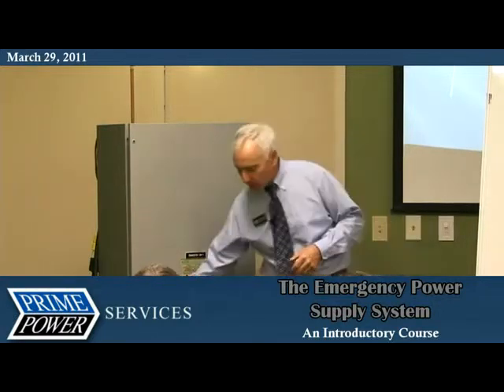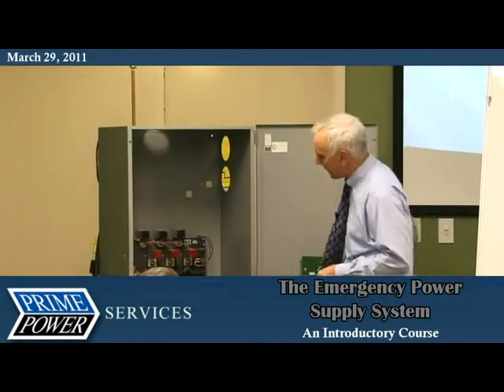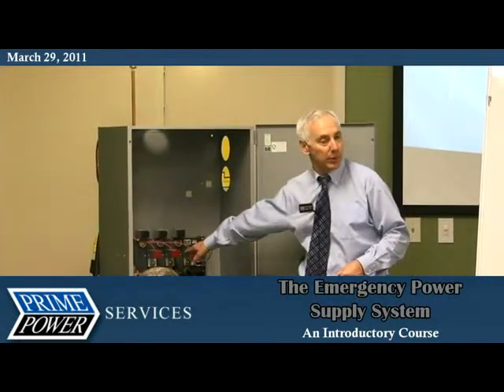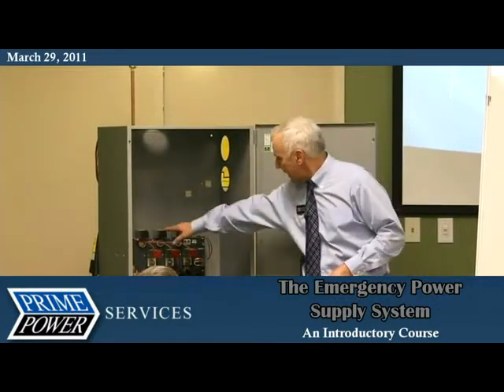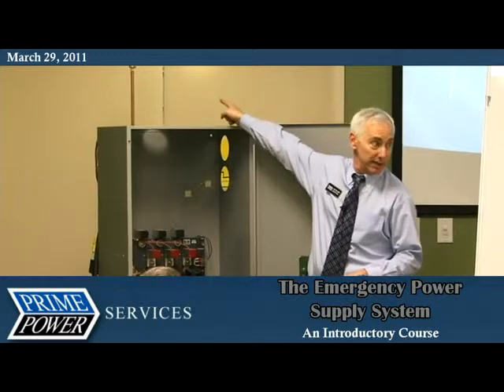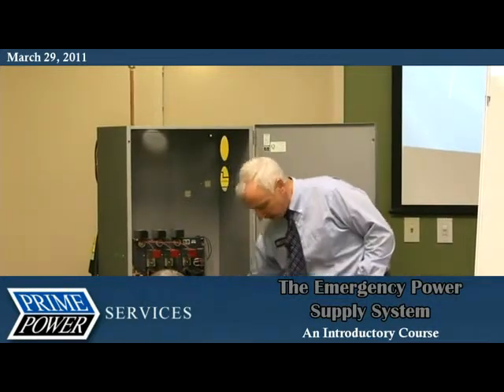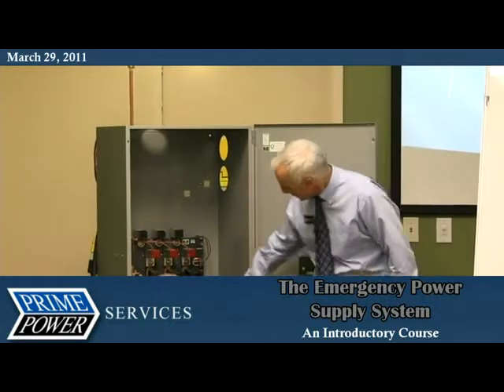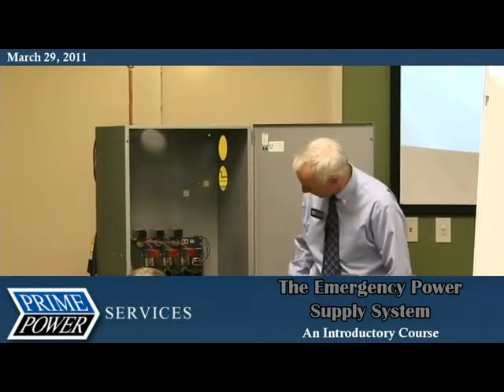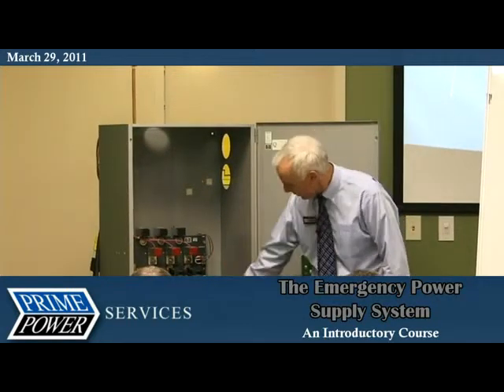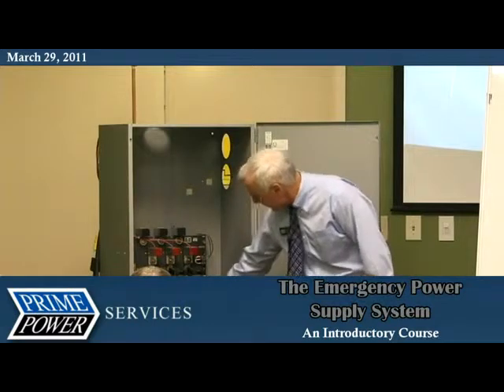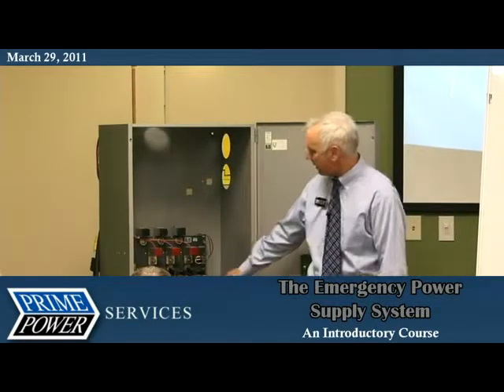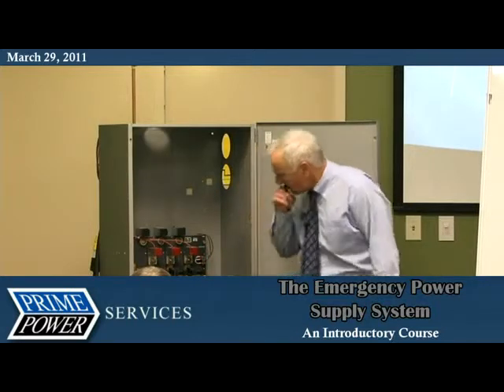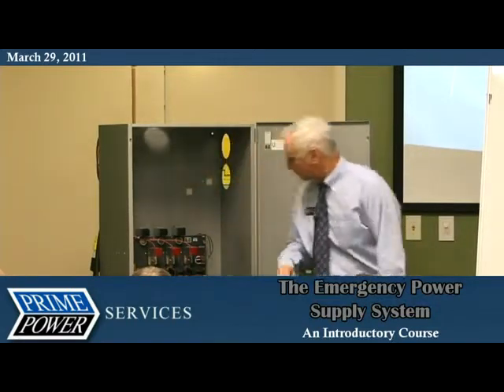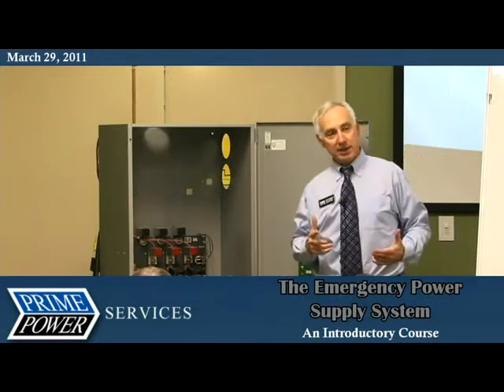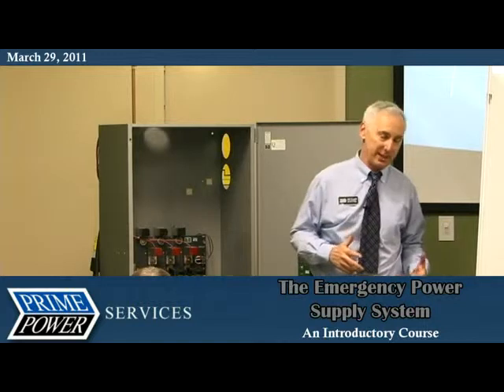When we look inside here, I've painted the contacts: red up top, or in the middle is emergency; the black in back goes out to the load, this light bulb. On the bottom, white is emergency power. These movable contacts we see here are normal power—did I say emergency? That's normal, excuse me. You see this set open and this set closed, and it says it's in normal. So let's just watch this—it all happens in the 1/6 of a second when it actually transfers.